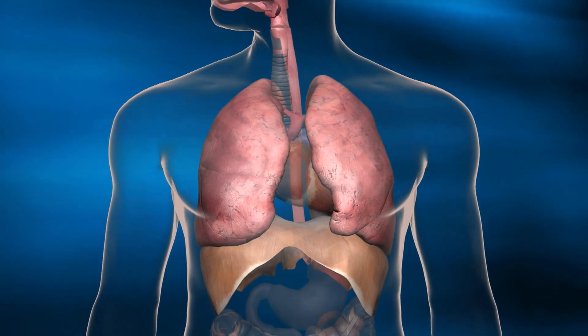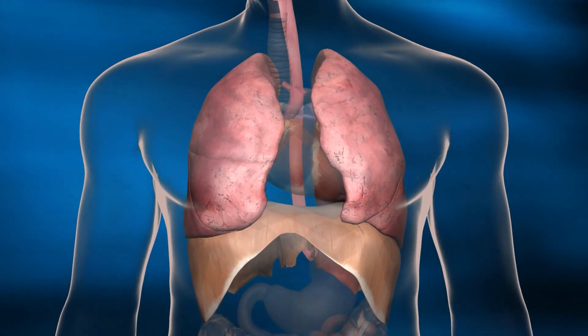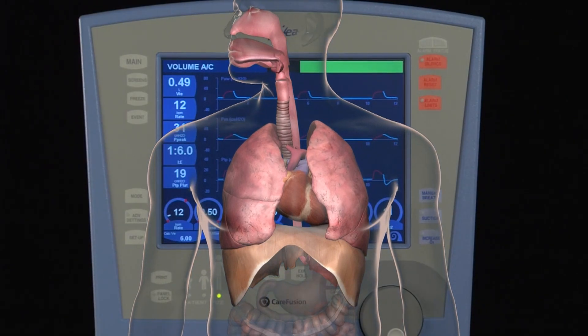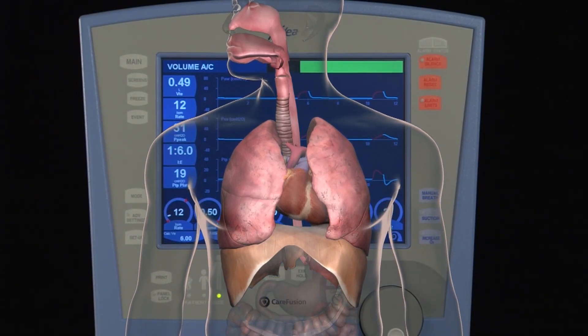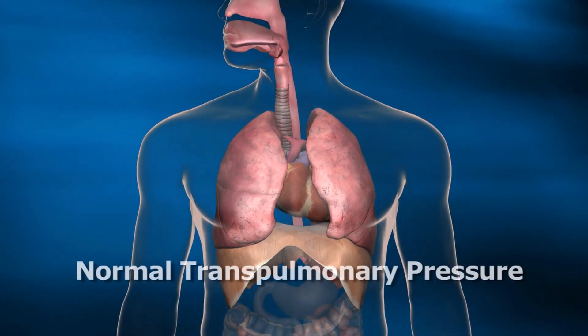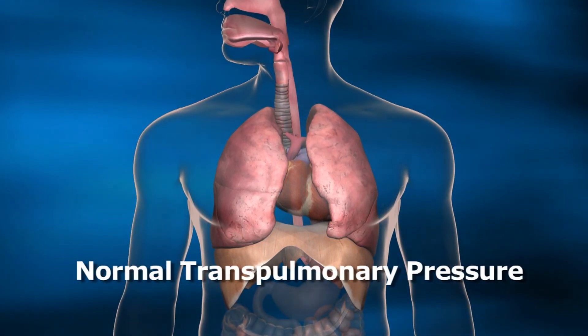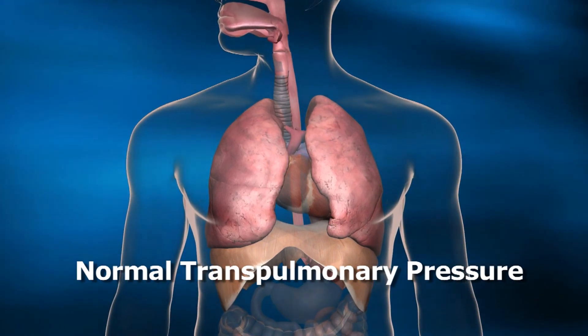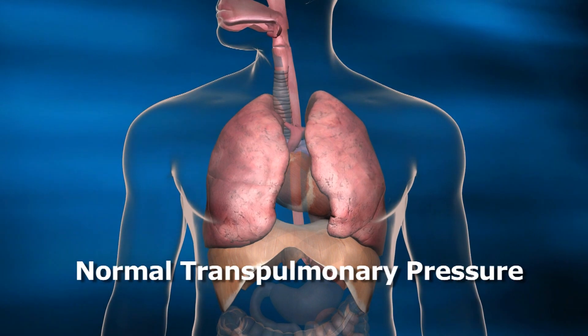Esophageal Manometry, which helps to provide the transpulmonary pressure value, is the missing piece of the equation. The Avea Ventilator not only provides the esophageal measurements, but calculates the transpulmonary pressure. Transpulmonary Pressure reflects the lung inflation pressure and excludes the effect of chest wall compliance as a cause of elevated airway pressures.